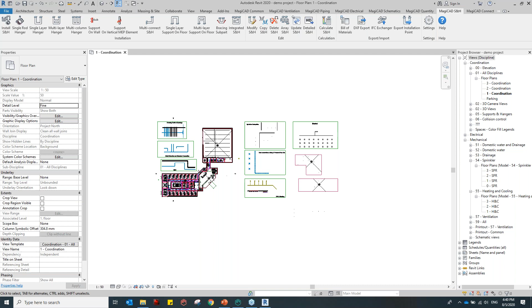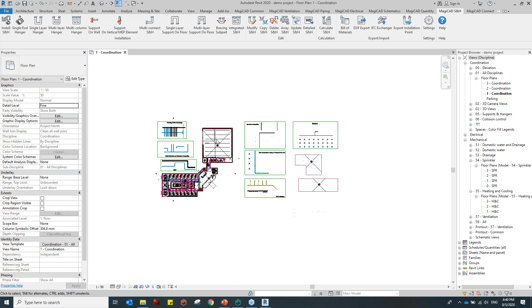Can we use a wet riser system in MagiCAD? Yes, of course we can use a wet riser system. It can be done, which is pretty similar to the hydrant system. So you can do the pressure drop and flow calculations for that. We use normal velocity or pressure loss methods to do the sizing.